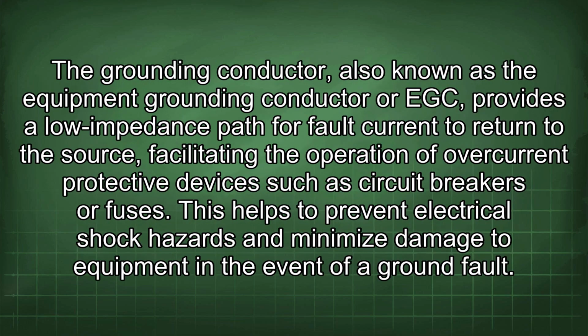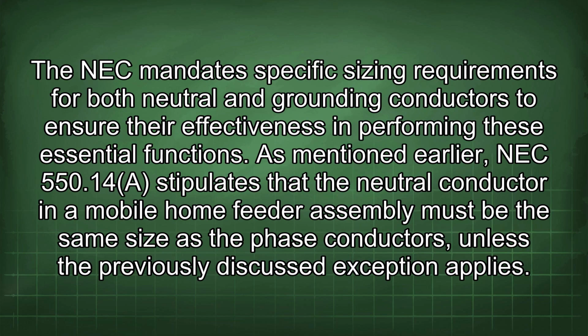The grounding conductor, also known as the equipment grounding conductor or EGC, provides a low impedance path for fault current to return to the source, facilitating the operation of overcurrent protective devices such as circuit breakers or fuses. This helps to prevent electrical shock hazards and minimize damage to equipment in the event of a ground fault.